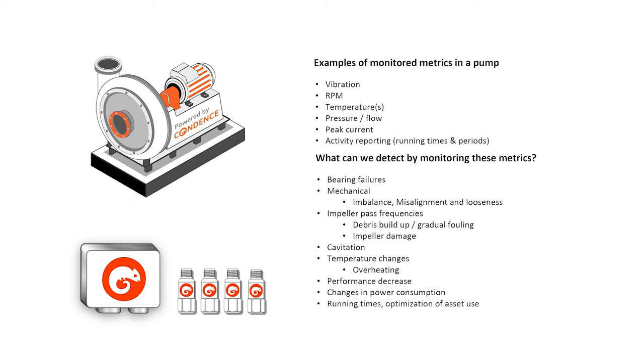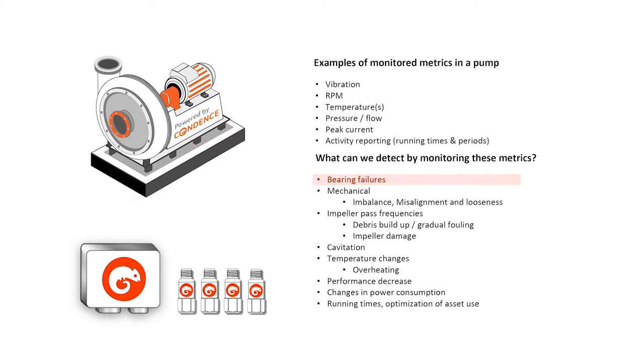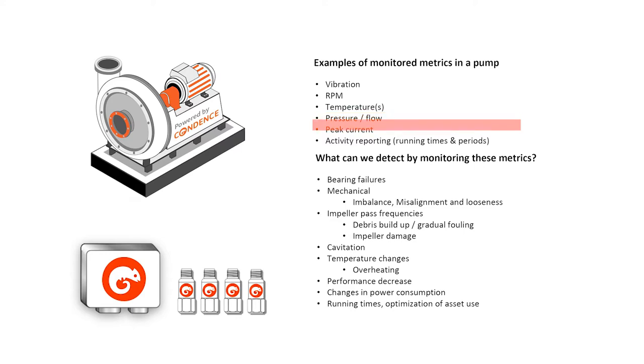Key indicators such as ISO standard overall value, device specific such as blade pass frequency, component specific such as bearing failure frequencies, process measurements such as pressure to indicate a problem like leakage change, and supplementary measurements such as peak current to indicate a problem like motor issues.